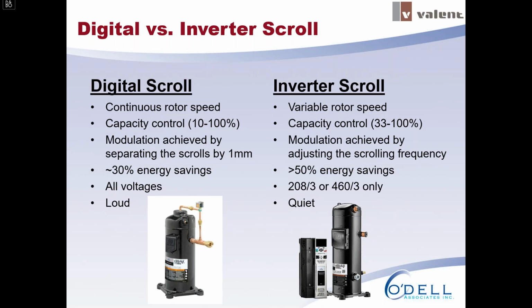Compared to a standard scroll, you're going to get about a 30% energy savings with a digital and over 50% energy savings with an inverter scroll. The digital scroll comes in all voltages, and currently the inverter scroll is only available at 208 and 460 volt. So aside from being more efficient, the inverter scroll is actually a lot quieter when it's operating, and it's noticeably quieter. Digital scroll, especially when it's unloading, tends to be loud and noisy, and if it's a sound sensitive application, digital scroll is probably not the right solution.